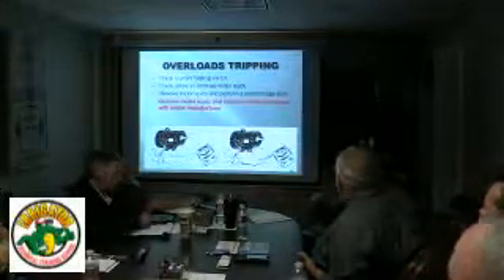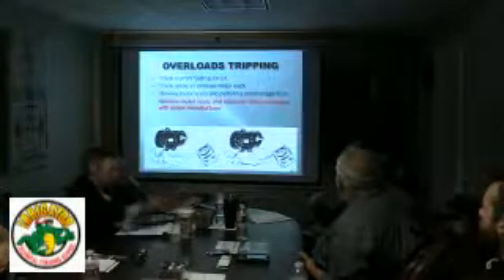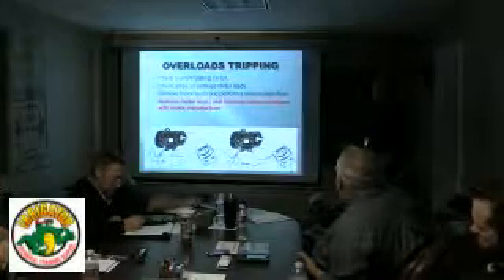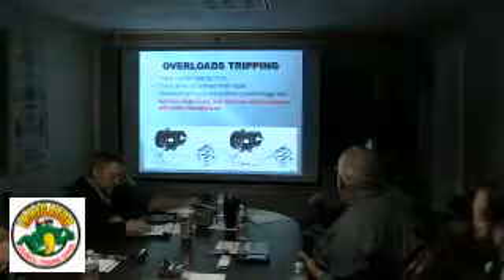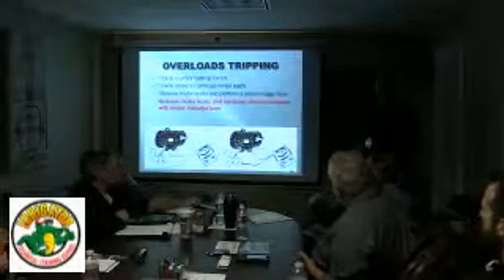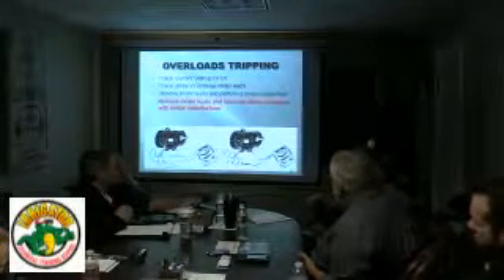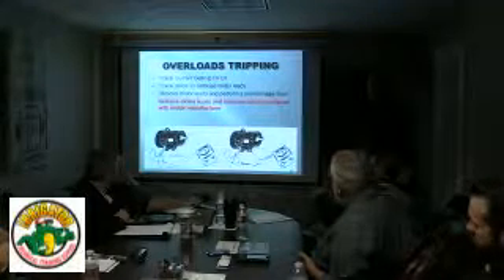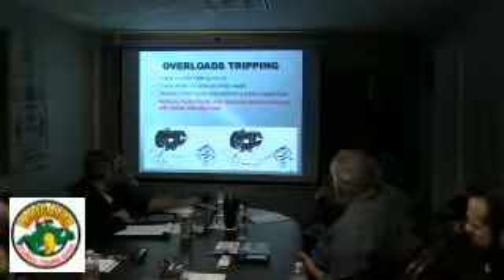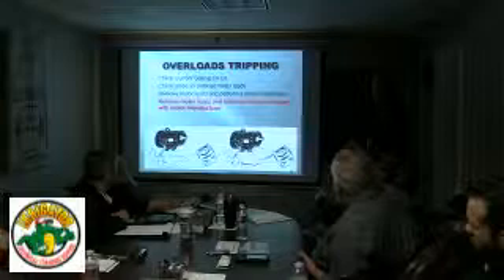So really what you're looking for when you're doing this is some kind of an imbalance. Measure from lead to lead, T1, T3. If you're getting like a half ohm between these two and a half between these two, and then you measure the other one and it's open or way over or a short, at this point you're looking for some kind of imbalance rather than trying to match it up to exact motor manufacturers. If there's not any big imbalance, everything seems fine. There's a good chance that the motor's okay. You also want to check each motor lead to ground. That should be open.